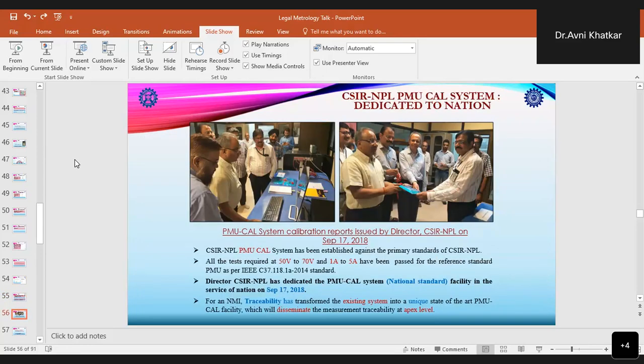And this CSIR NPL PMU calibration system was dedicated to the nation in 2018. It is established against the primary standards of CSIR NPL. All the tests which are done using the PMU calibration system are done from a voltage range of 50 volts to 70 volts, and at currents of 1 ampere up to 5 amperes, at different reporting rates as per the requirement of the test.